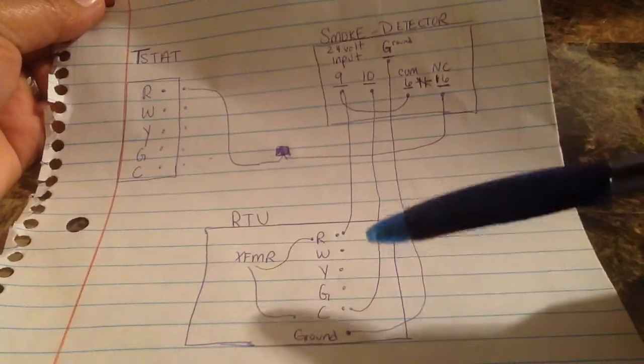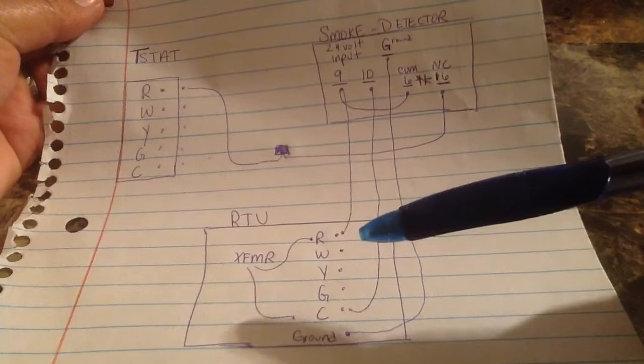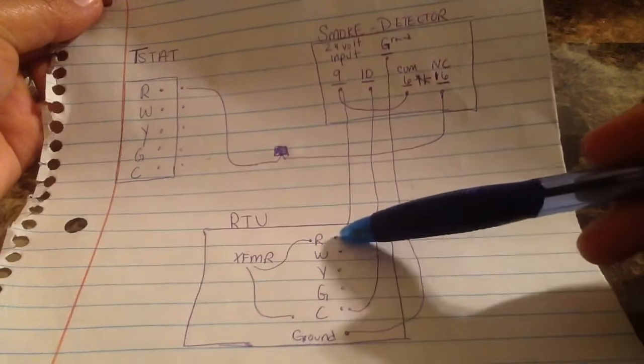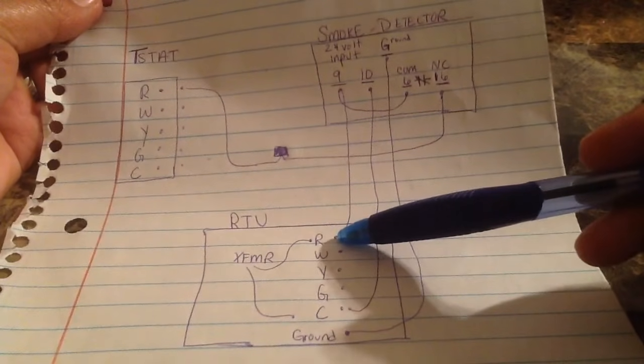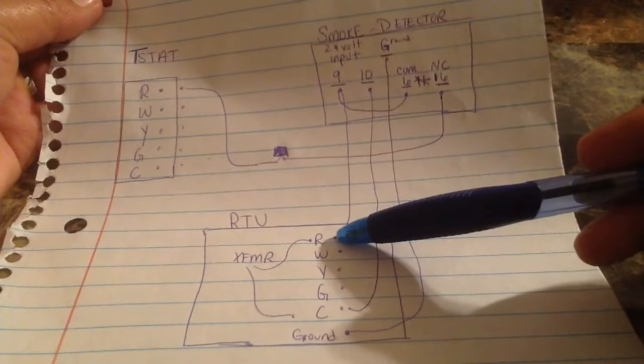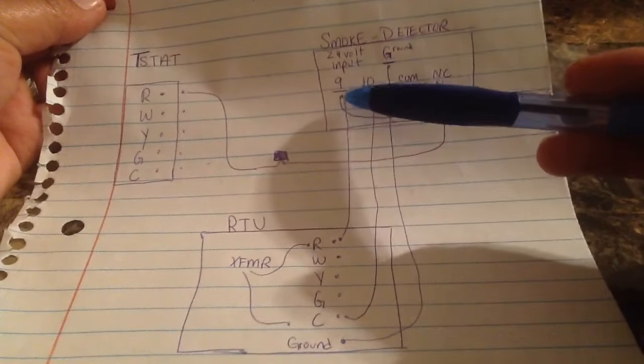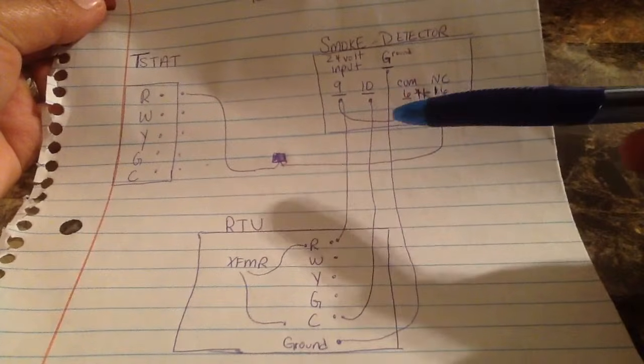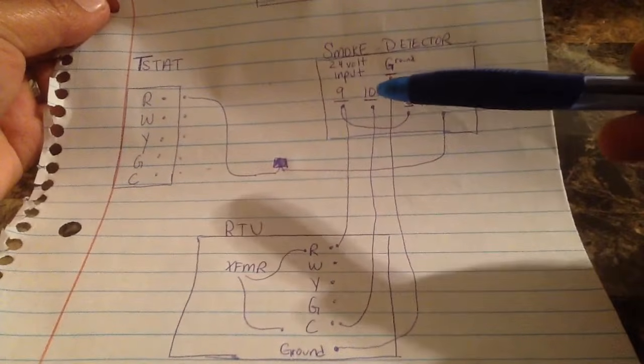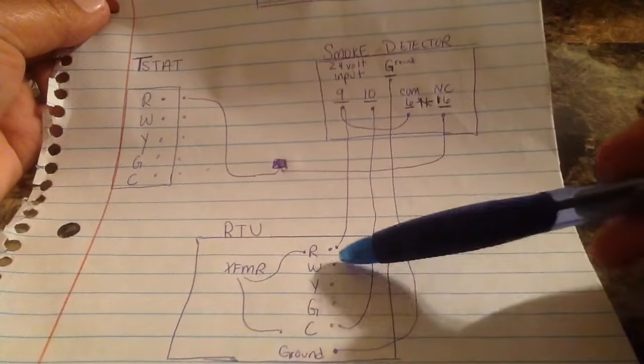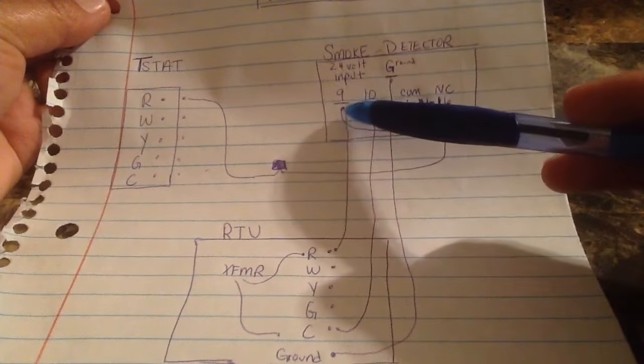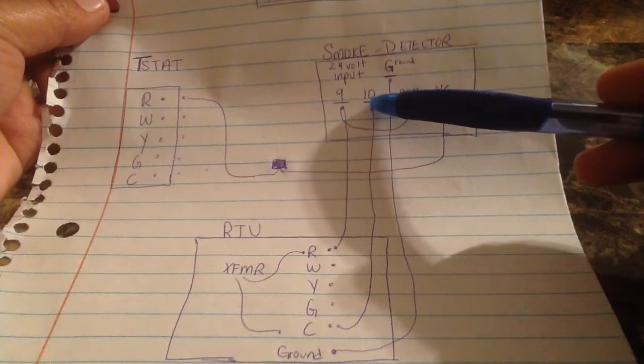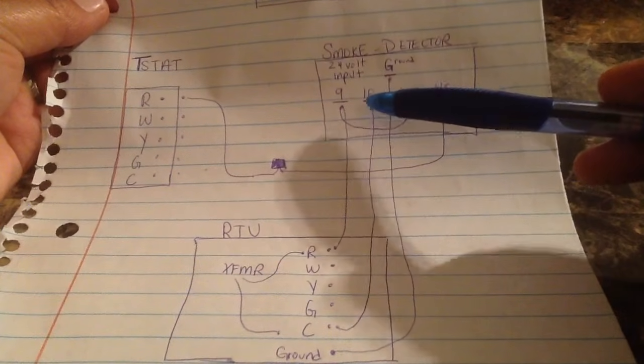One of the four wires I'm running, I'm stealing power at the R terminal strip at the rooftop and I'm going up to, typically most smoke detectors are going to use nine and ten are going to be your 24 volt input to power up the detector. So 24 volt R goes to nine, common goes to ten. That's powering up the smoke detector.